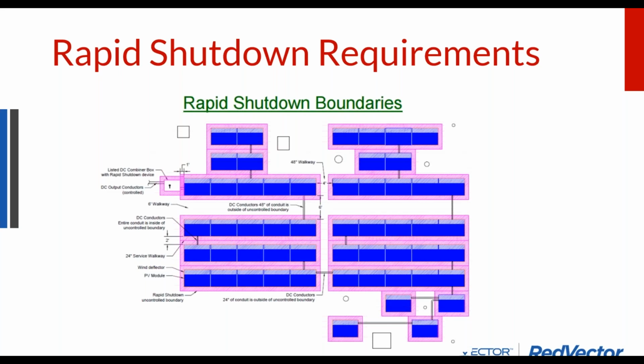In the past, rapid shutdown was a lot more loose. They say, well, as long as you can turn the array off outside of the array, de-energize the conductors between the array and where it's connected on the ground, you're fine. But ever since rapid shutdown was first introduced to code, and I think in 2014, the perimeter has shrunk. It used to be 10 feet around the array you could remain energized. And then it shrunk down to 1 foot around the array it could remain energized.